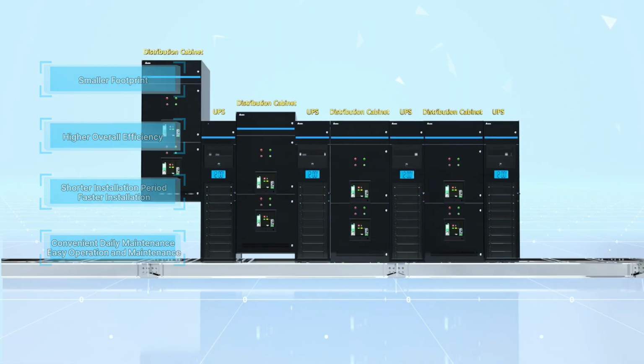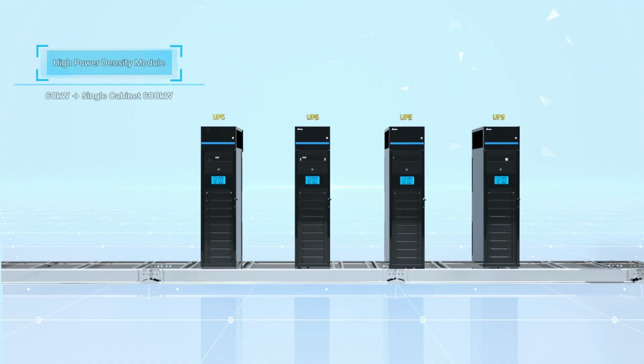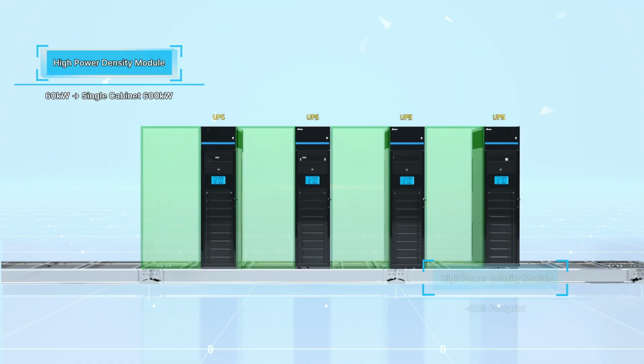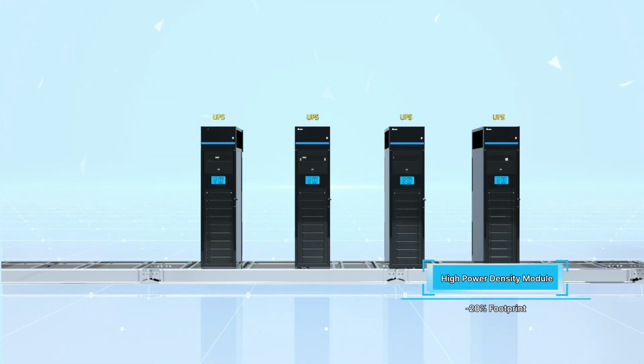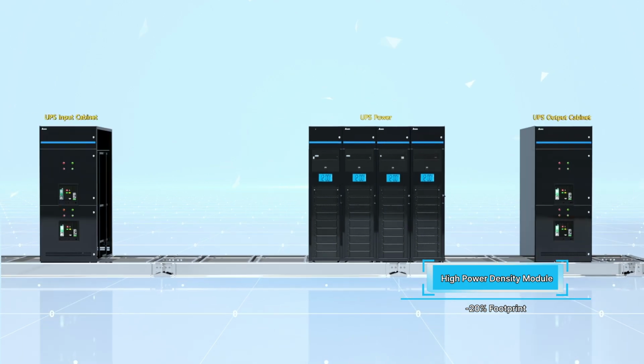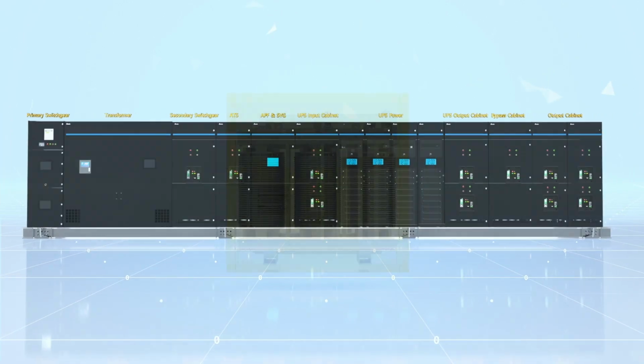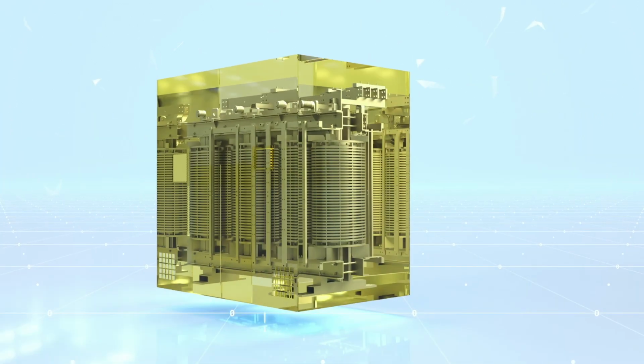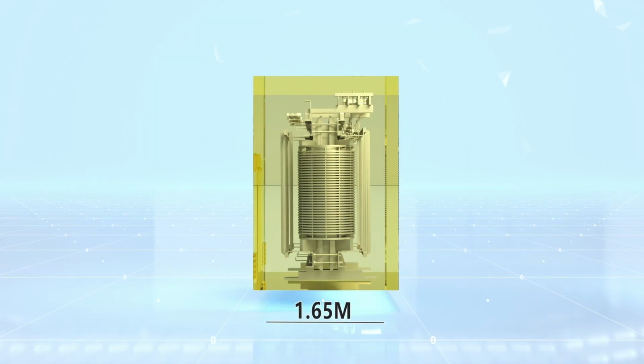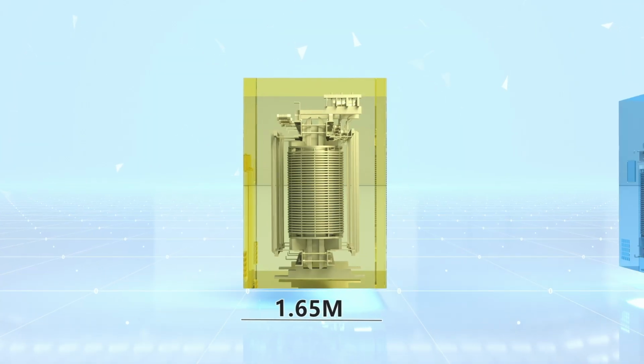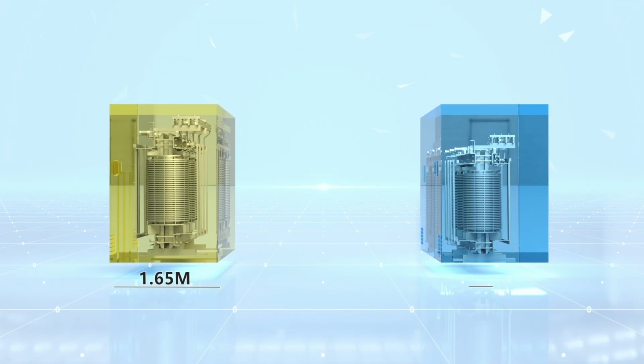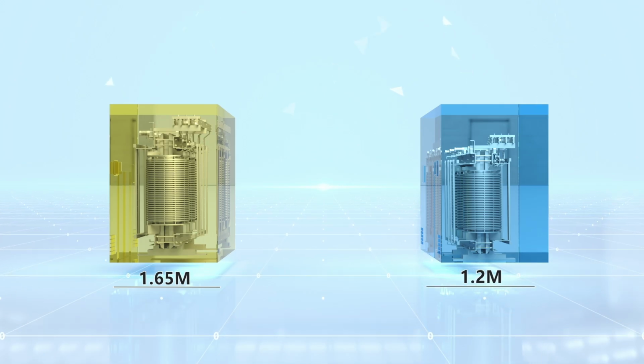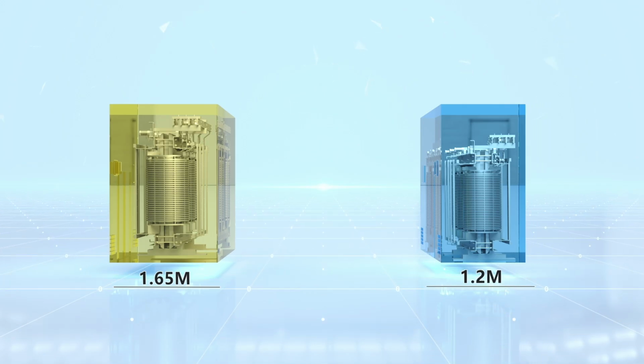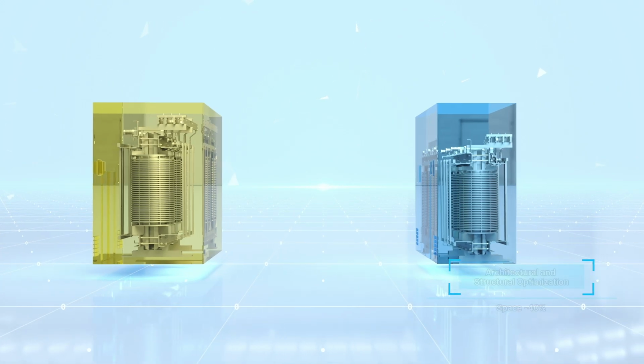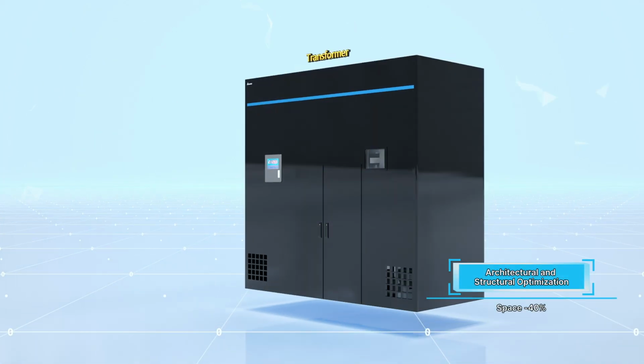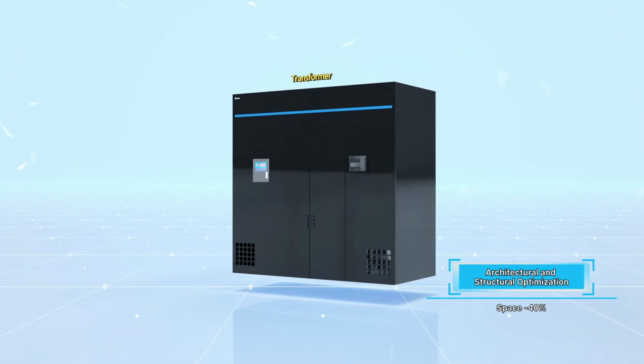By optimizing the integration of low-voltage distribution and UPSs, it can save 20% of application space compared to traditional UPS power systems. In comparison to similar products on the market with a transformer cabinet depth of 1.65 meters, Delta has optimized the cabinet's internal structure, reducing the depth of the entire row of transformer cabinets to 1.2 meters. With 40% space savings, users gain more space to deploy server cabinets.